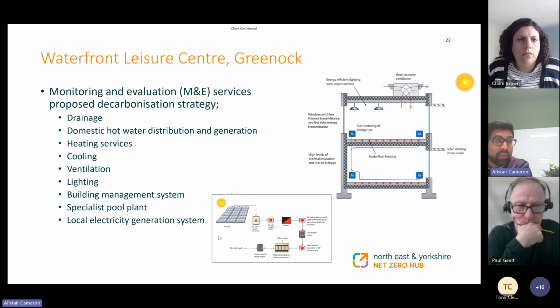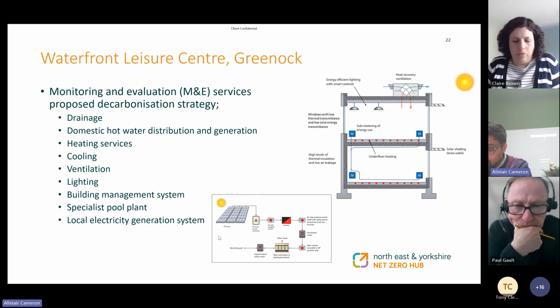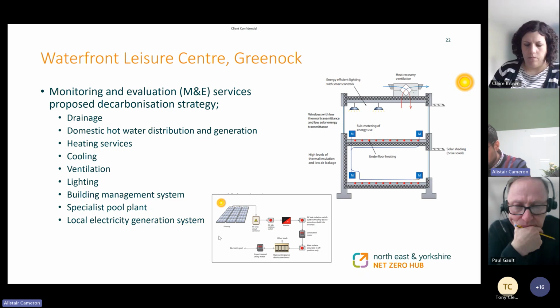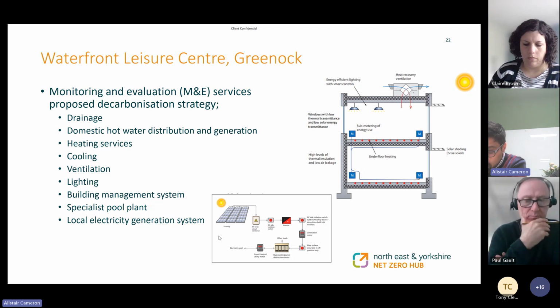Domestic hot water, with the high number of changing facilities and showers, there is a lot of stored water in the building, and there's a lot of distribution pipework in the building. The domestic hot water vessels and the pipework haven't really been upgraded since the building's original construction, and a lot of the insulation was generally of poor quality. So we felt that immediately you could enhance the insulation on the pipework, you could enhance the storage vessels' insulation levels, and you could also look at reducing the amount of hot water storage in order to reduce storage loss associated with the hot water distribution system.